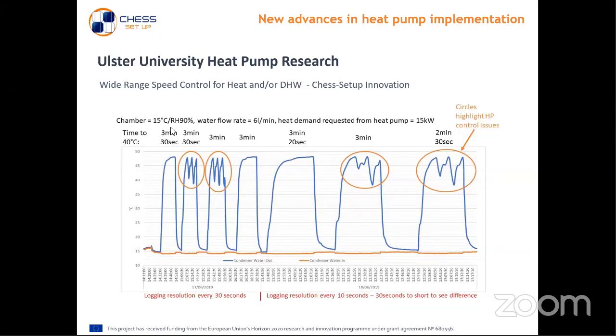So one of the challenges that came out very quickly when we started working with the variable speed drive compressors and how much they can actually deliver across their speed range is technically, you can't have them running too quickly or they damage. And if you go too slowly, they don't lubricate properly. But an unknown challenge, which came quite a surprise to the manufacturers as well, was these control instabilities that we came across. So you would try and ramp up a compressor and come up to, say, deliver hot water as quickly as possible, and then the compressor would become unstable.